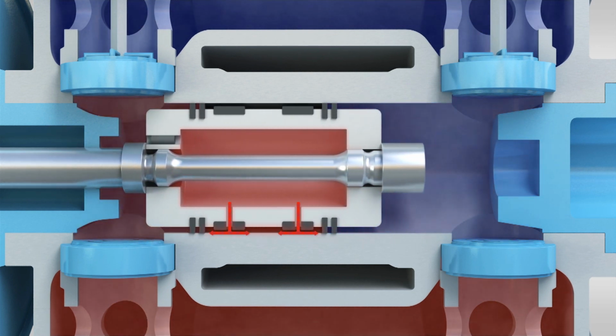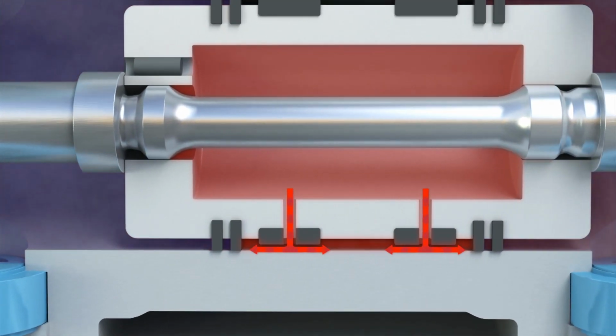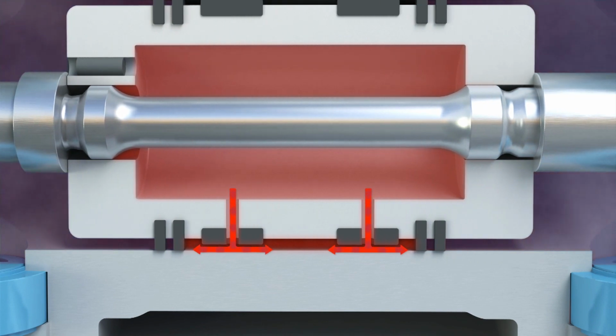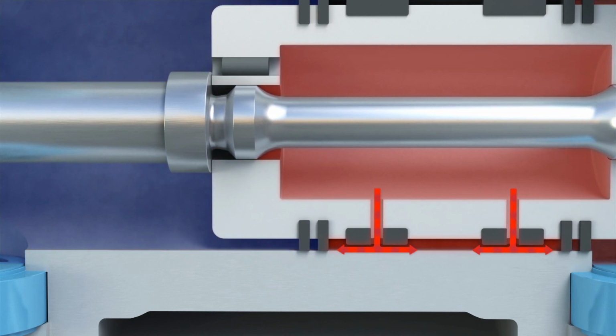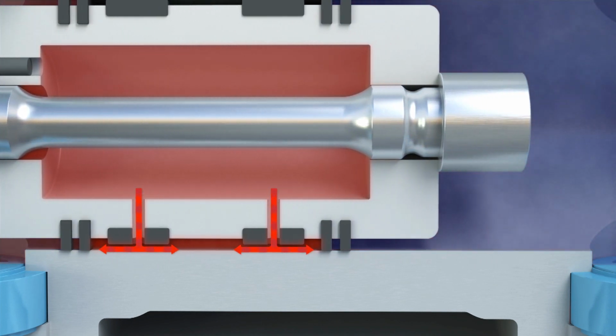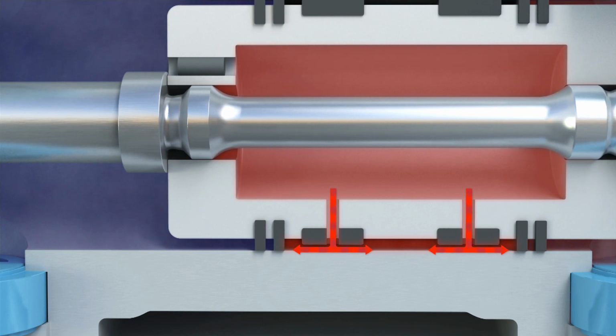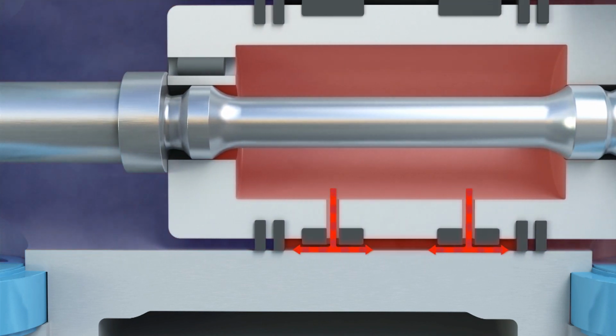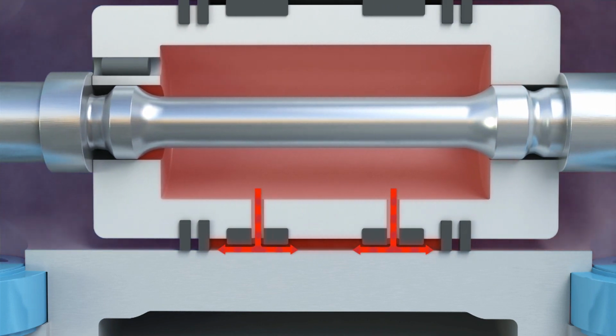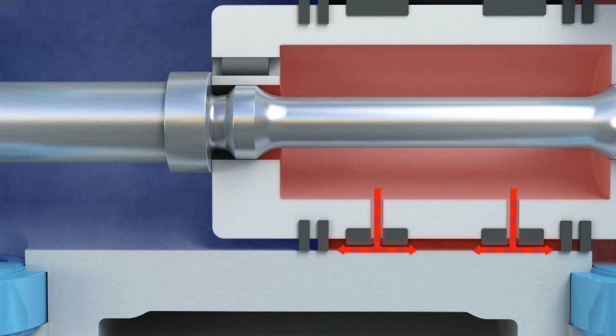The design of the piston has also been specially adapted. The rider rings are now relocated in between the piston rings to create a constant pressure. Regular compressor valves that react to differences in gas pressures are located in the piston face, enabling gas to enter into the piston. Flow nozzles have been integrated in the rider rings and a profile machined on the lower surface to create a bearing layer beneath the piston.